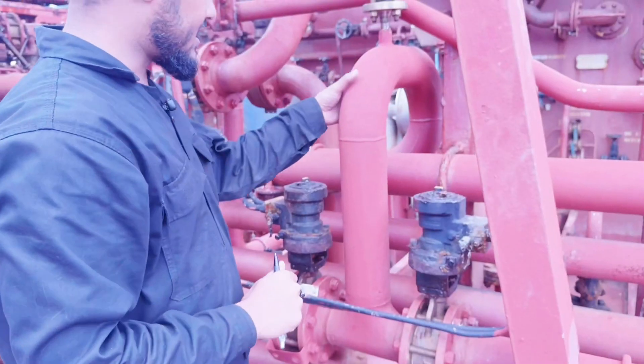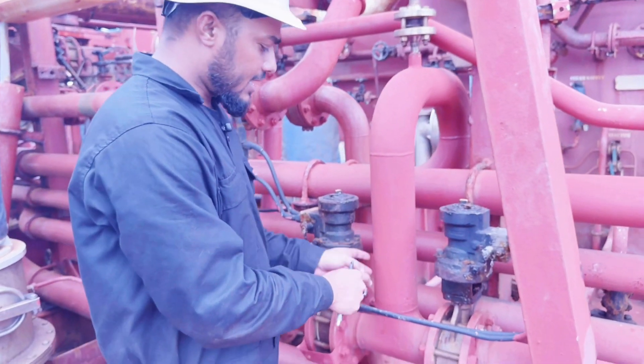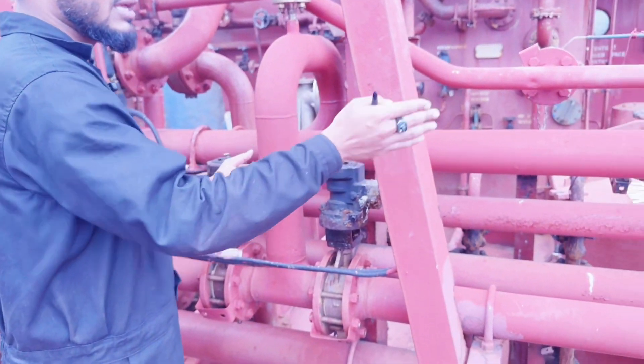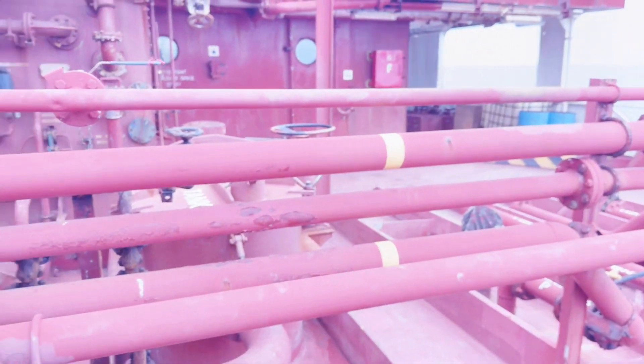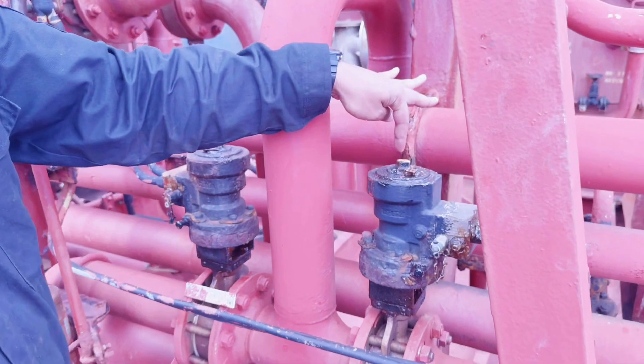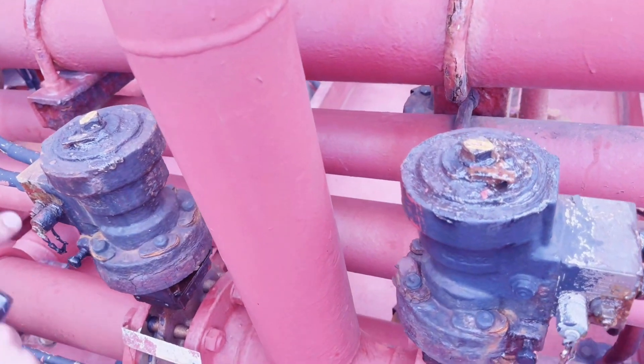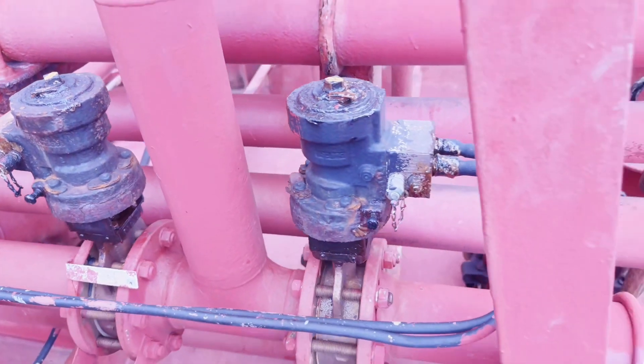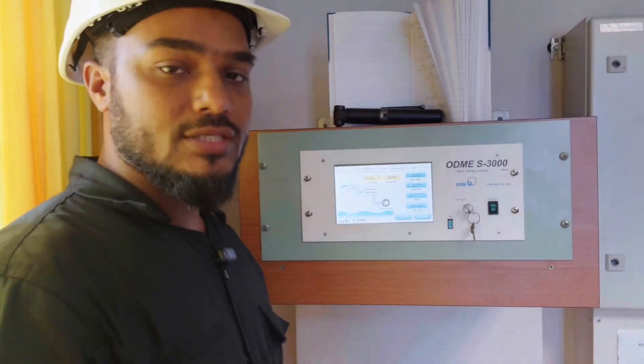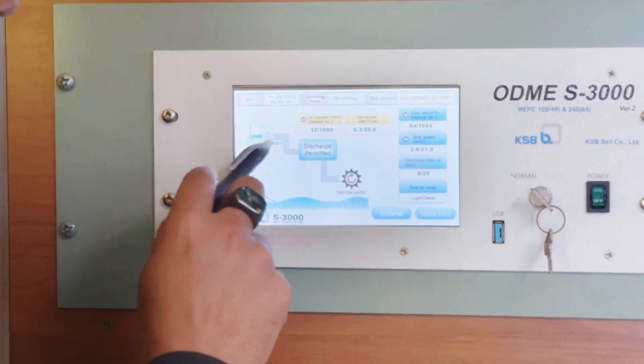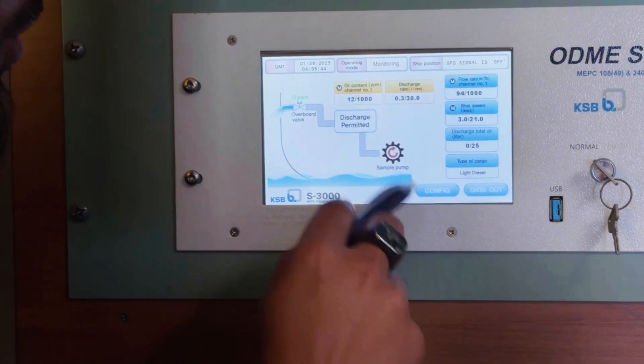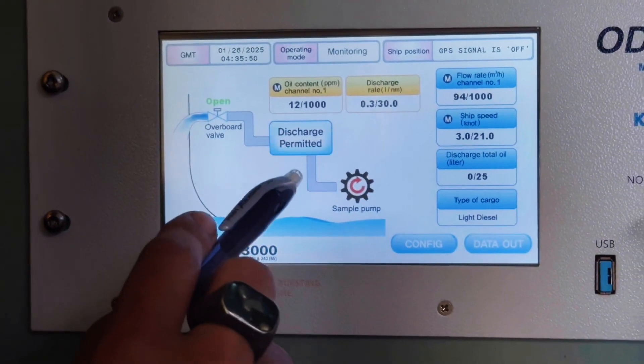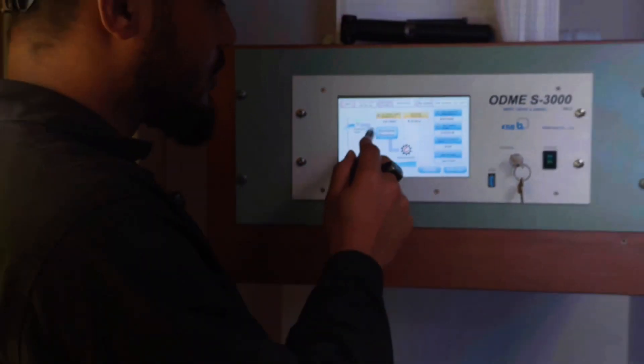This return line is coming from the slop tank, and it is either going back to the slop tank through this valve or going to the discharge line. You can see this valve is in discharge mode — it is open, meaning it is allowing discharge and not allowing return to the slop tank. Back at the CCR, it is showing 'discharge permitted,' which means in simulation mode your discharge is permitted.